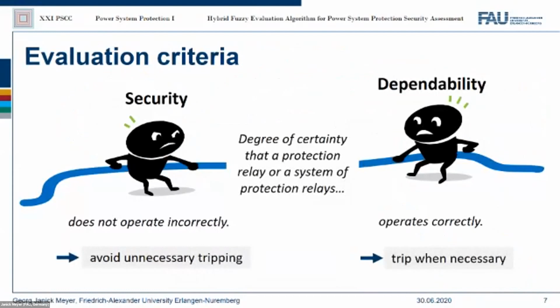Two of the most important criteria when assessing power system protection are dependability and security. Dependability is defined as the degree of certainty that a protection relay or a system of protection relays operates correctly. In contrast, the definition of security is that a protection relay or a system of protection relays does not operate incorrectly. Specifically, this means that dependability indicates whether a protection relay trips when it's necessary. Security, on the other hand, is the ability to avoid unnecessary tripping behavior in all operation conditions, as well as short circuits and faults outside of the relevant zones, and is therefore closely linked to the notion of selectivity.